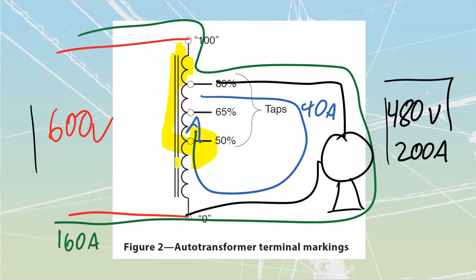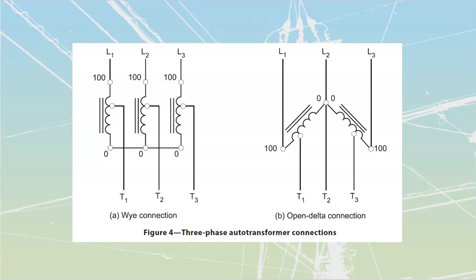All in all, it's a wonderful thing because now we took this 600 volt motor that initially was starting out at 250 amps as inrush. Now, by putting it onto this autotransformer, we are only going to drop the thing down to 160. The motor still gets 200 amps. It's a fairly significant amount of current there. But by the time I go through the transformation to the high side, we've dropped this down to 160 amps. It's just a significant change. And we really like this because it makes everything much easier on our electrical system.